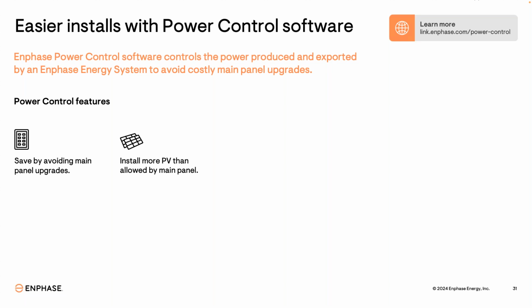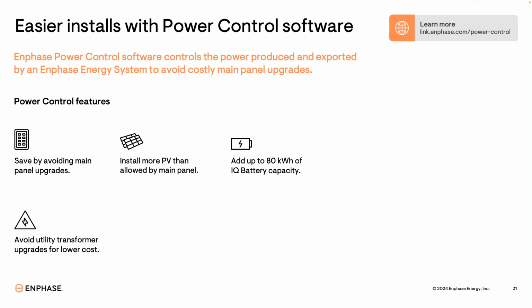It can be used for solar-only systems to install more PV than normally allowed by the NEC 120% rule. It allows you to add up to 80 kilowatt hours of IQ battery capacity, whereas previously there was a limit of 40 kilowatt hours. It can also control current exported to the utility grid, which helps avoid costly utility transformer upgrades. And in select markets, it allows the battery to export power back to the utility grid as well.